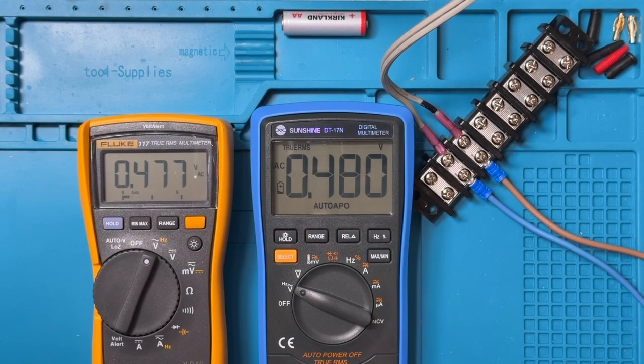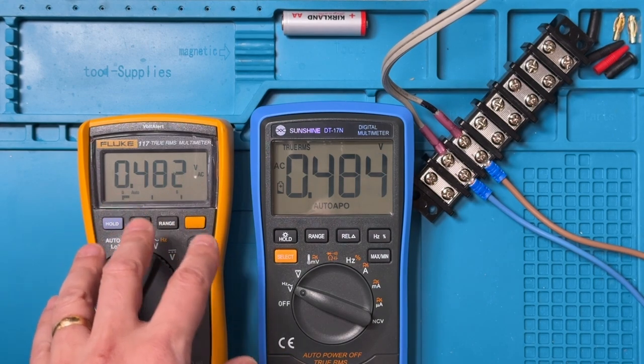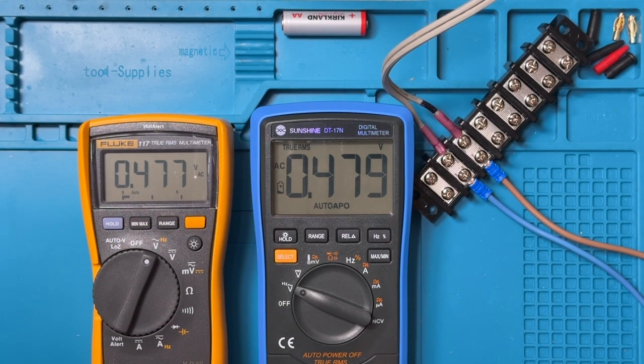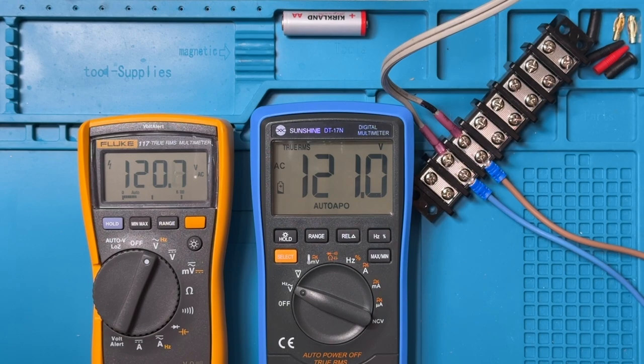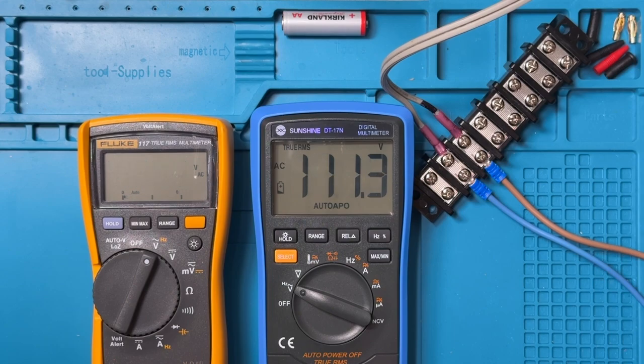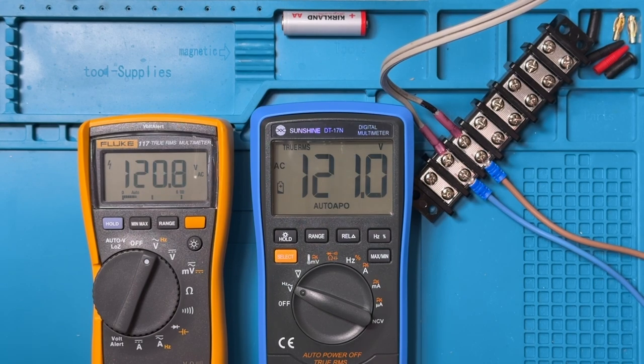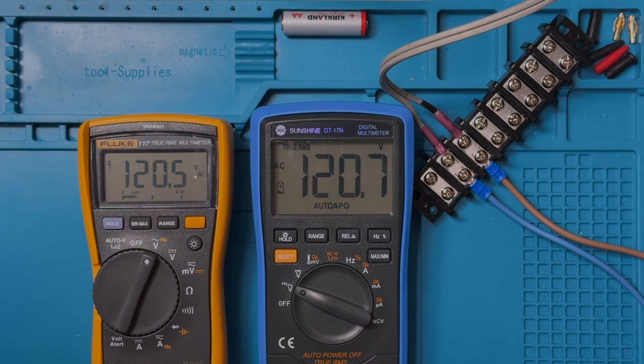Now for AC voltage, I'm going to compare against this Fluke 117 because I don't have an AC reference source. So we'll just see how the two track and the Fluke is pretty accurate. So right now the power is off, so we're seeing a little bit of ghost voltage. So that was on. You can see that the voltage is pretty close to what the Fluke is showing, maybe off by a tenth of a volt. Now let's just check the response time. So that's off. On. So just a little bit slower than the Fluke, but still pretty good. Nothing to complain about there.